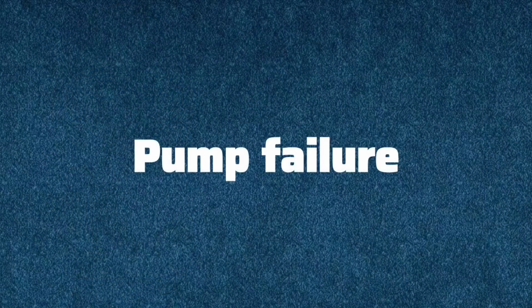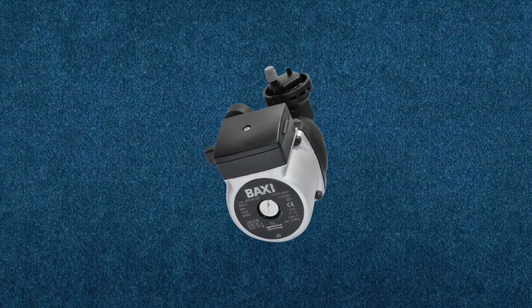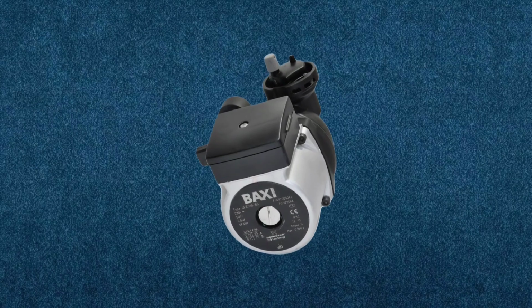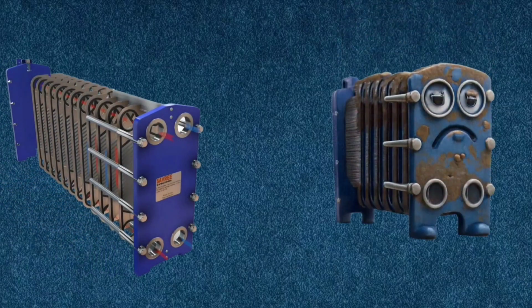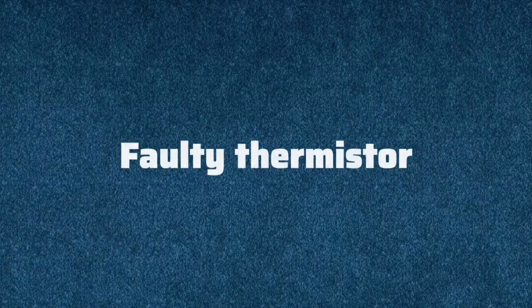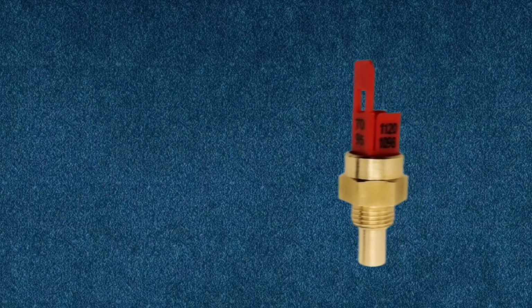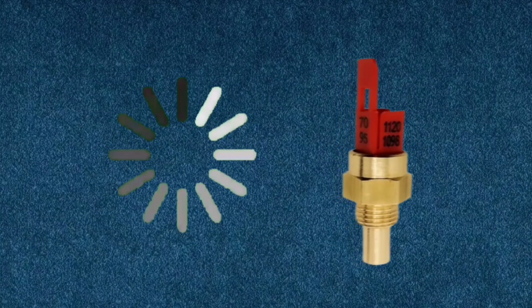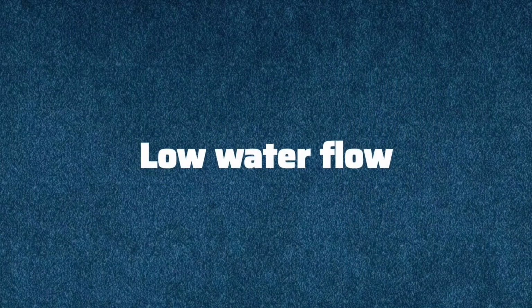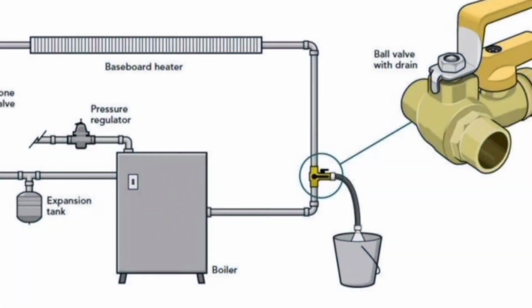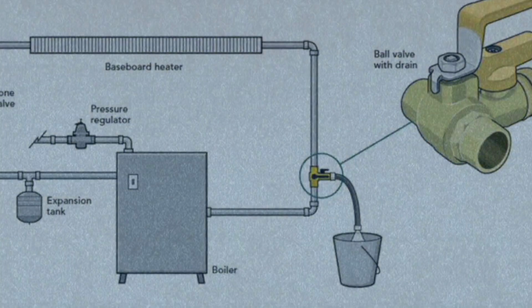Common causes include pump failure, where the pump isn't moving water so the boiler overheats; a blocked plate heat exchanger, where sludge or scale stops heat transfer; a faulty thermistor sending the wrong temperature signal; and low water flow caused by trapped air or closed valves restricting circulation.